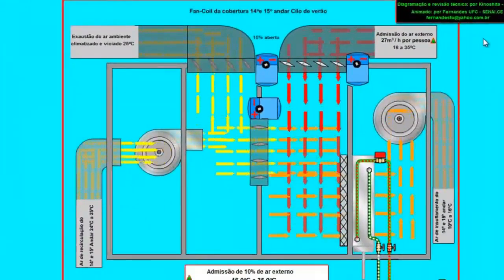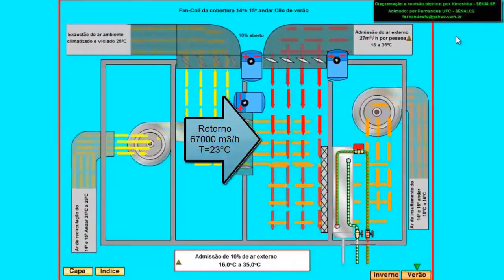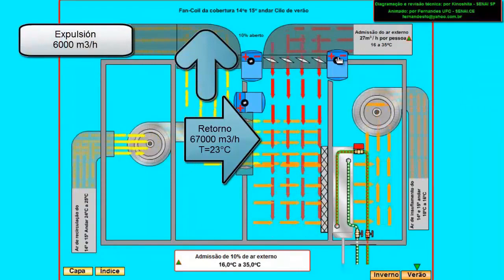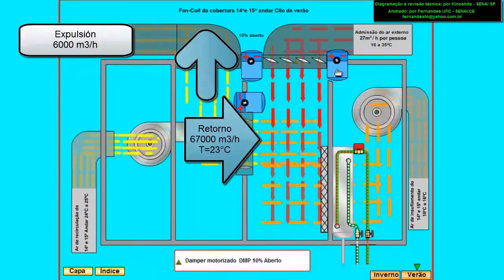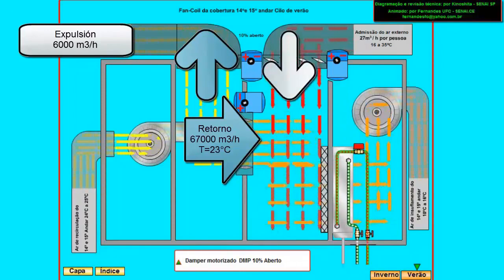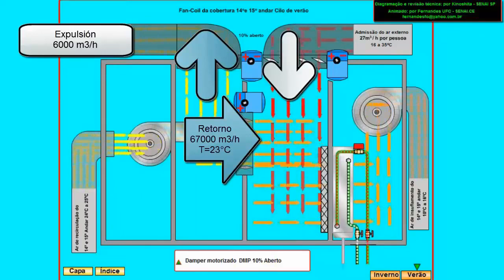Let's show the work points. 1. Return flow from the premises, with a value of 67,000 cubic meters per hour, at a temperature of 23 degrees Celsius. 2. Expulsion flow to the outside, with a value of 6,000 cubic meters per hour at 23 degrees Celsius. This percentage represents a loss of efficiency of the air handling unit, but it is justified by hygienic conditions. 3. Replacement flow, which comes from outside at a temperature of 35 degrees Celsius, with a value of 6,000 cubic meters per hour.